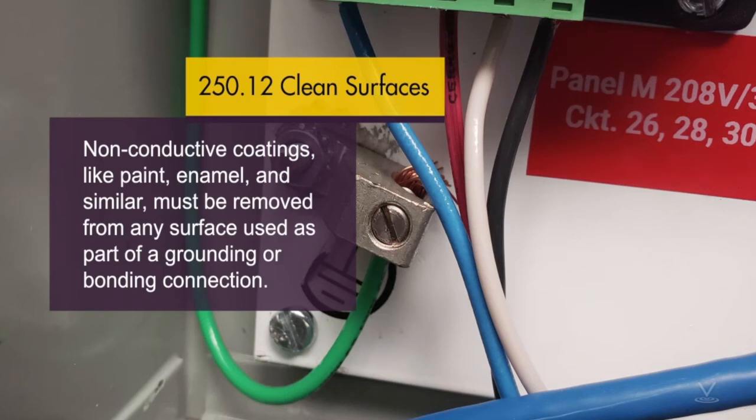Again, non-conductive coatings like paint, enamel, and similar must be removed from any surface that's used as part of a grounding or bonding connection. Not really a technical change—that's been in the code for a very long time—but just an editorial clarification.